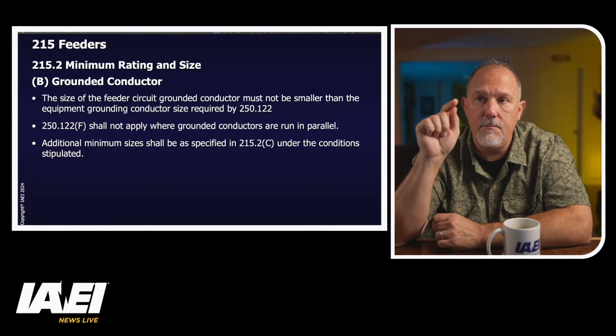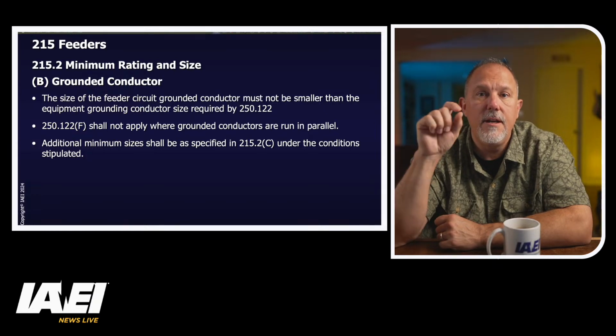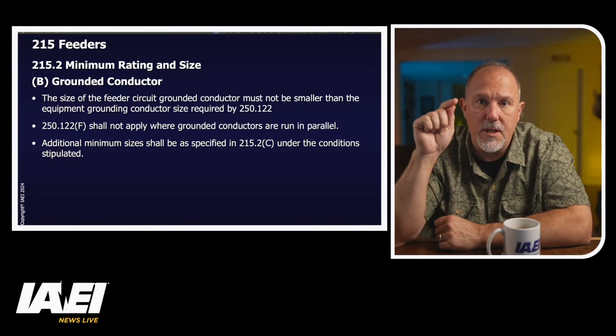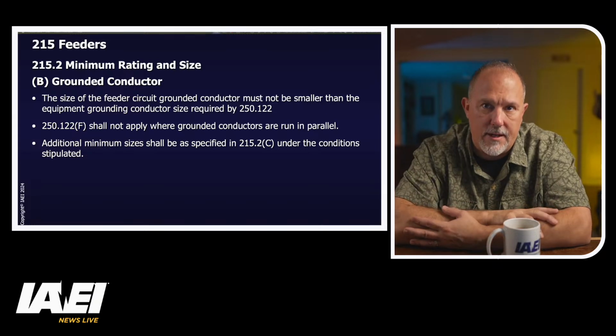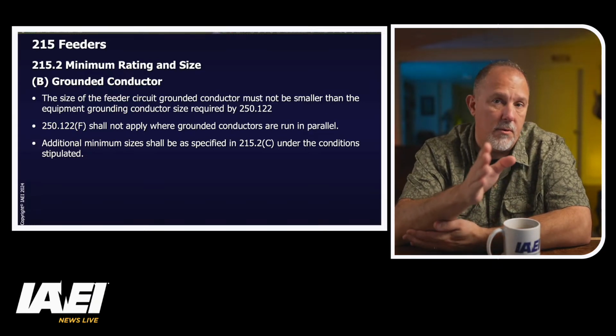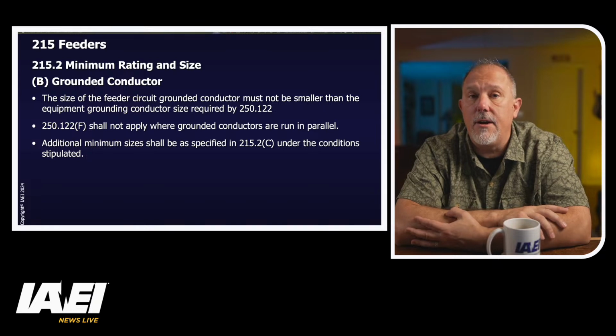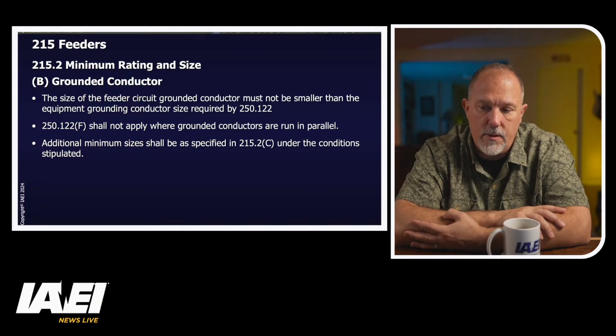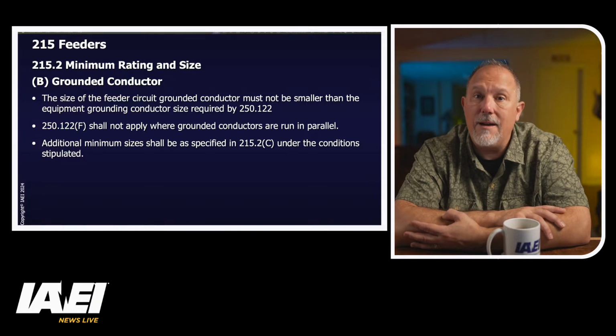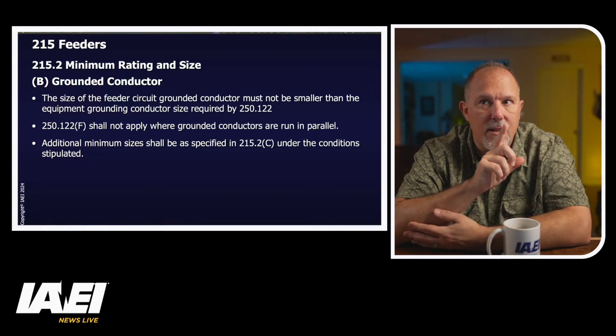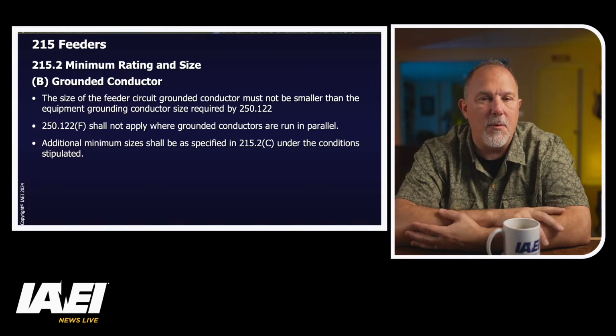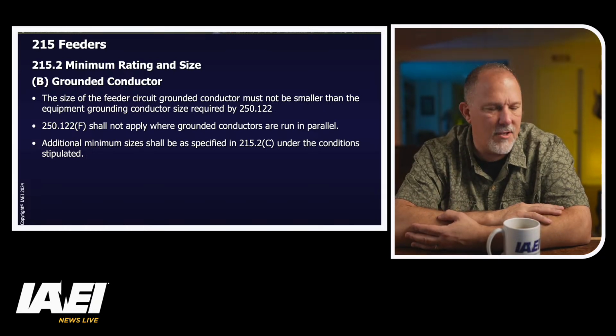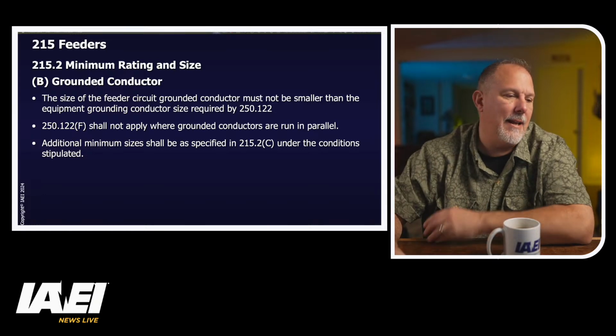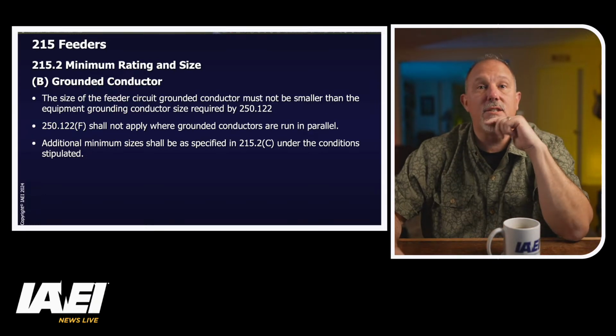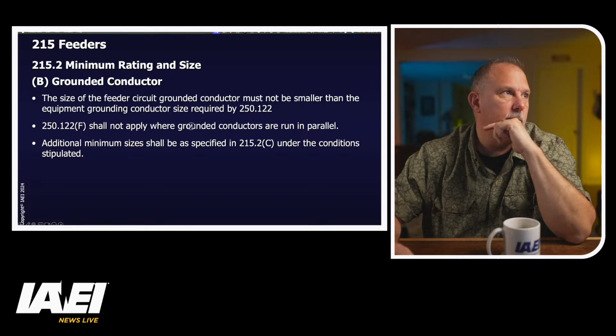I do not have to make the grounded conductor increase in size because of that increase in size of the equipment grounding conductor. So good point that you may find a scenario where the equipment grounding conductor exceeds the size of the grounded conductor, as long as it's not because of 250.122. Good point. I like it. I like it a lot. All right, so you got to remember 250.122.